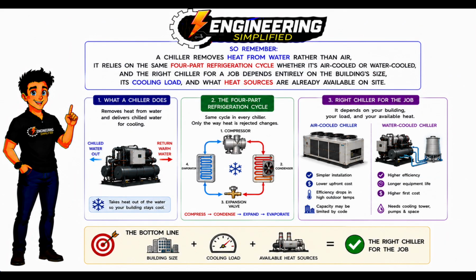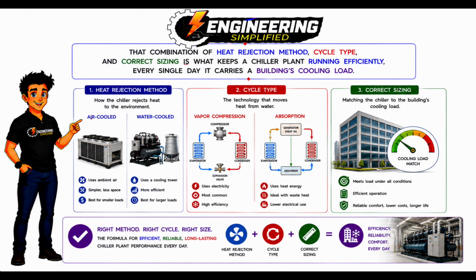So remember, a chiller removes heat from water rather than air. It relies on the same 4-part refrigeration cycle, whether it's air-cooled or water-cooled. And the right chiller for a job depends entirely on the building's size, its cooling load, and what heat sources are already available on site. That combination of heat rejection method, cycle type, and correct sizing is what keeps a chiller plant running efficiently every single day it carries a building's cooling load.